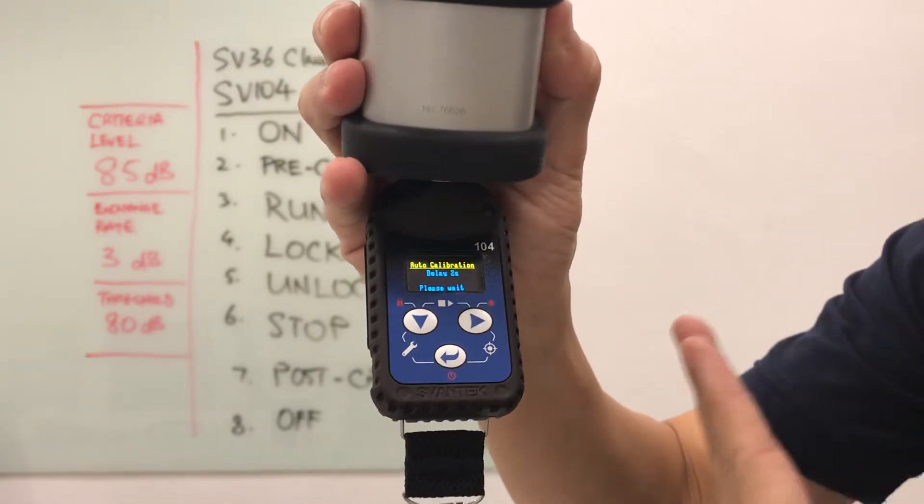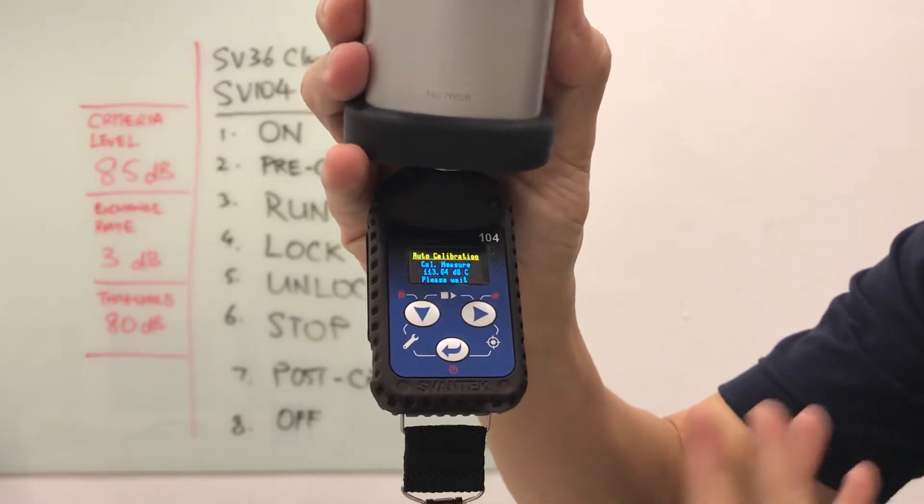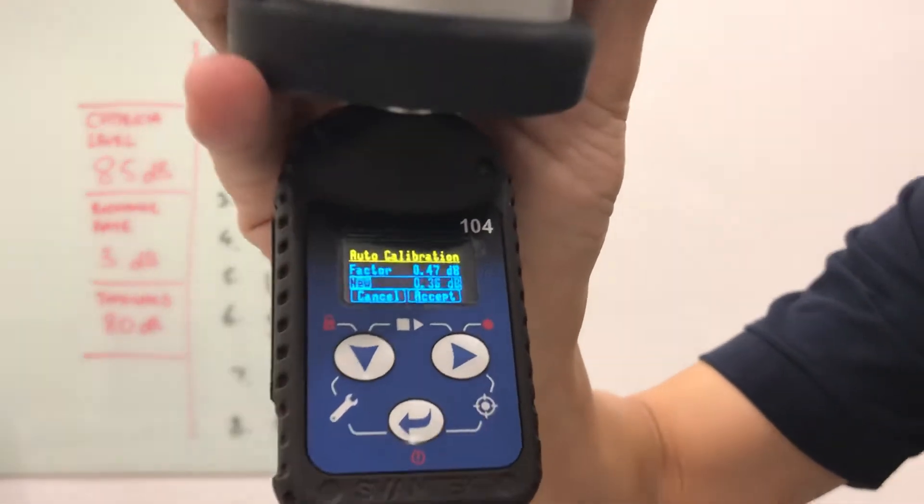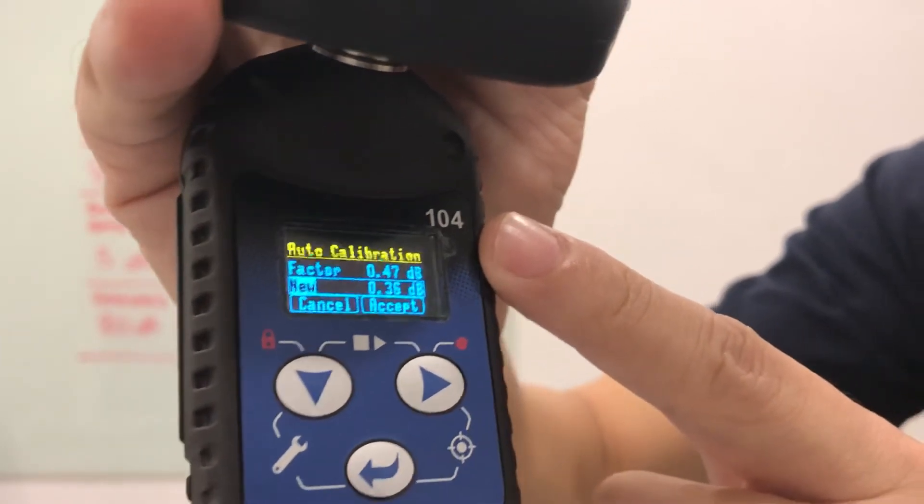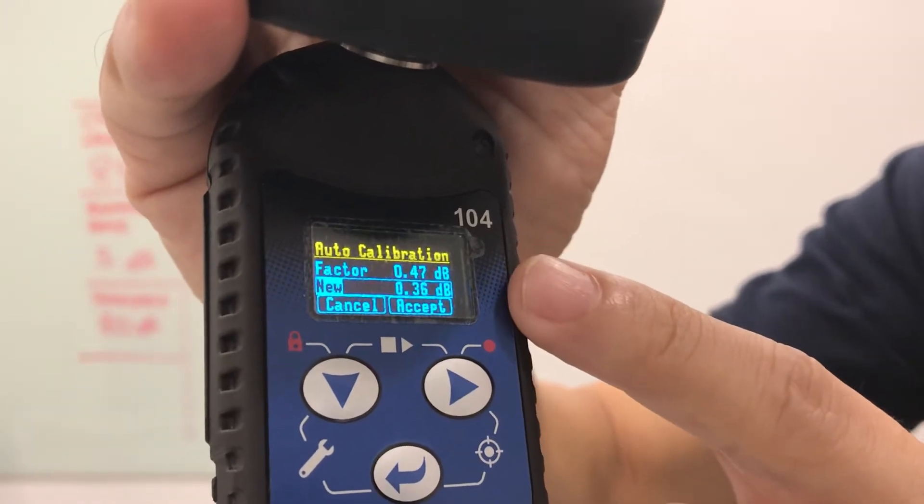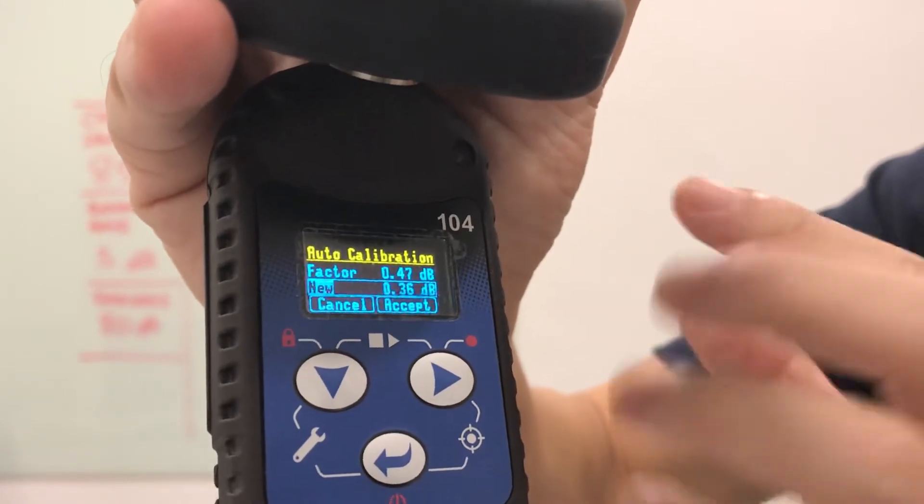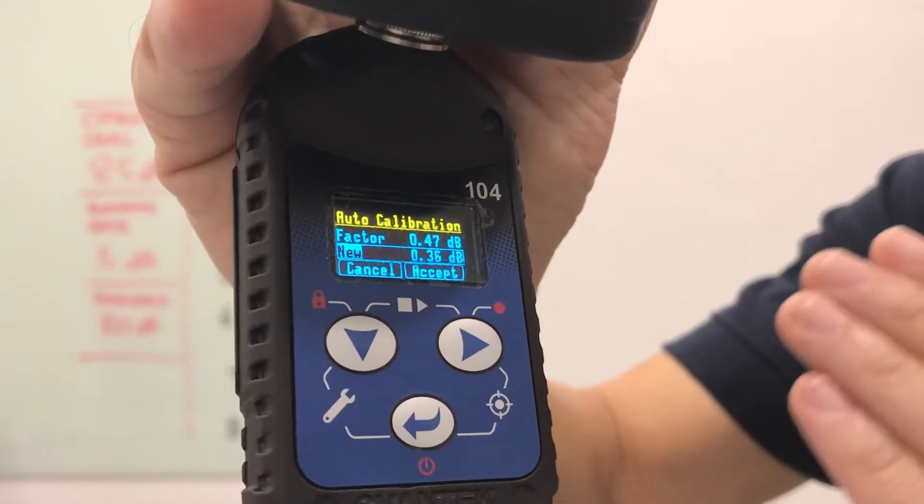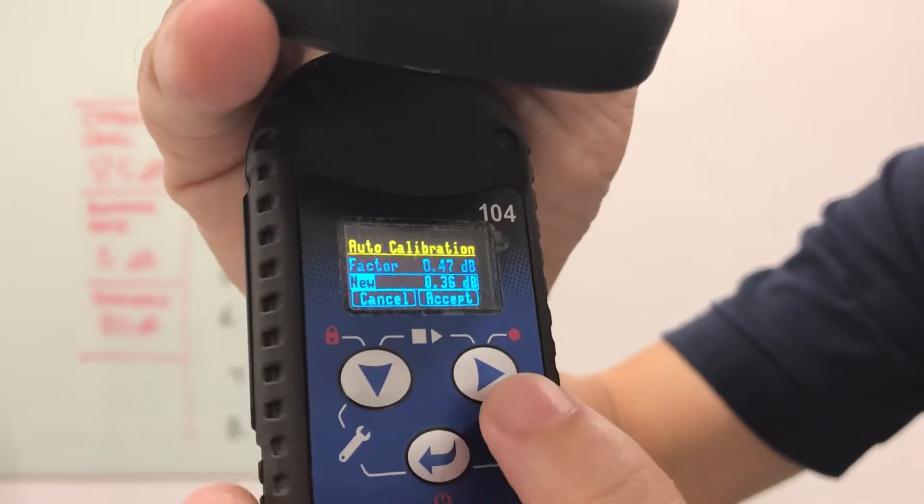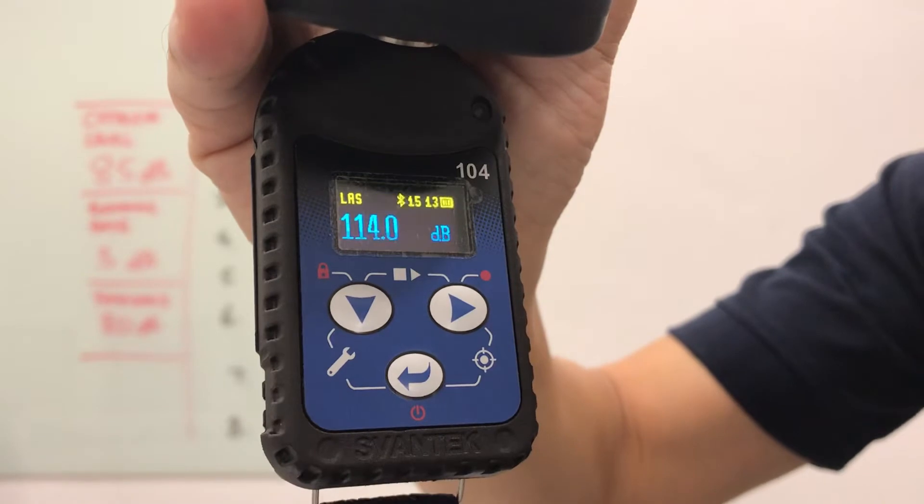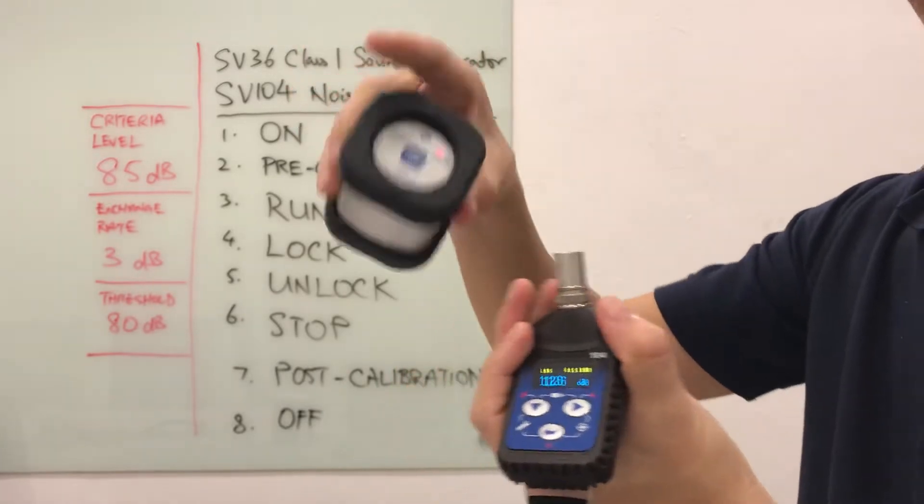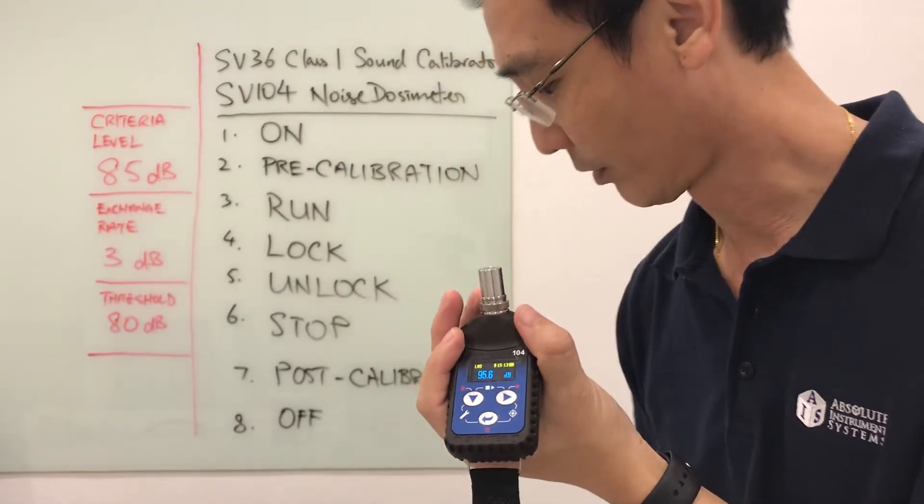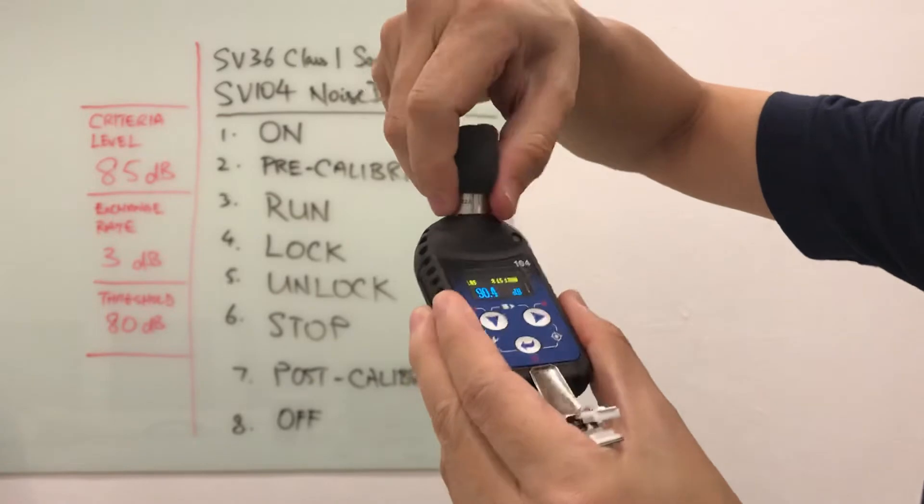Notice that the screen has turned itself off, that is a screen saver function. I pressed a button to reactivate the screen. On the screen right now, I can see we are going through auto calibration with a previous factor of 0.47 and the new factor is 0.36. There is a slight drift but this drift is acceptable as long as it's less than 0.5, we are still within the specification. I accept the new calibration factor, and the device is calibrated. I can now remove the calibrator and replace the windscreen.